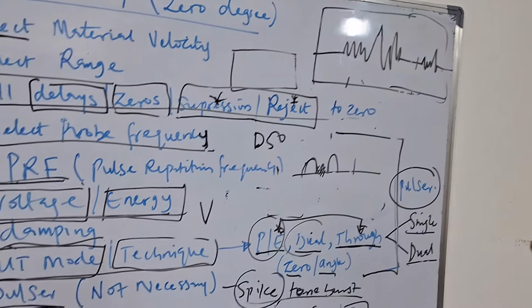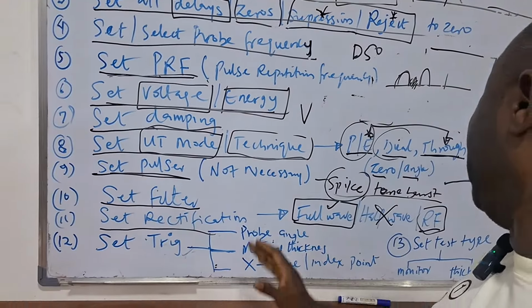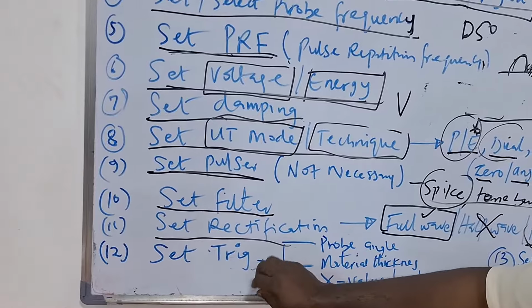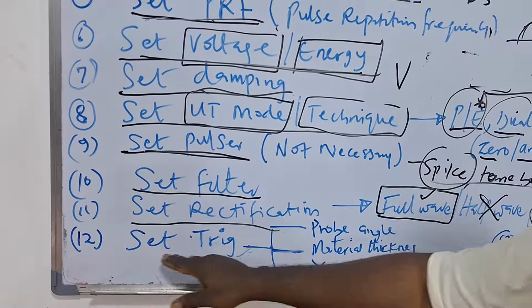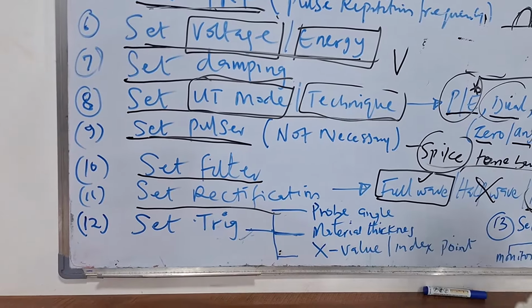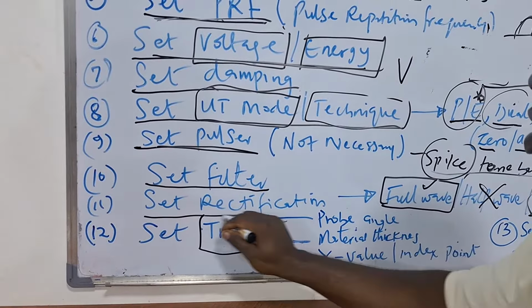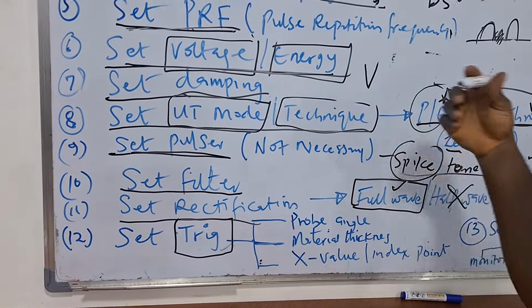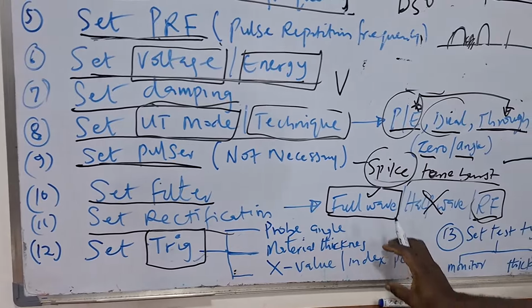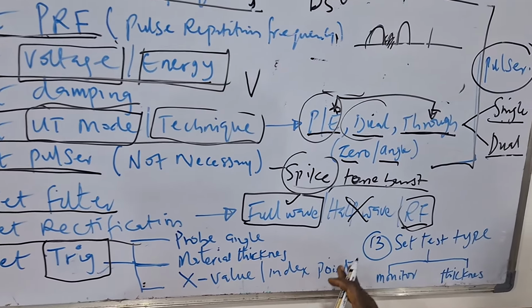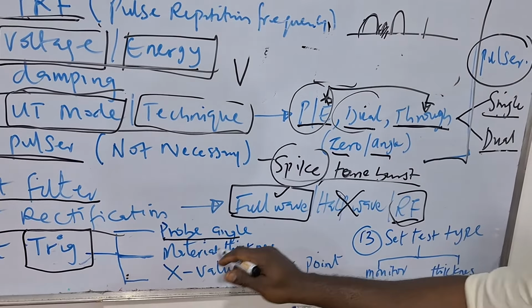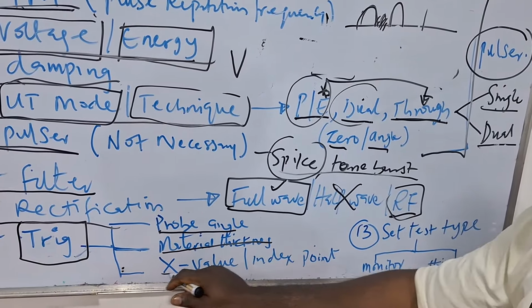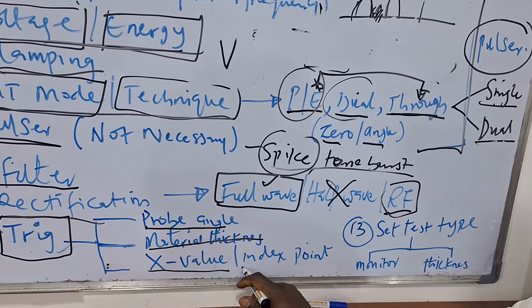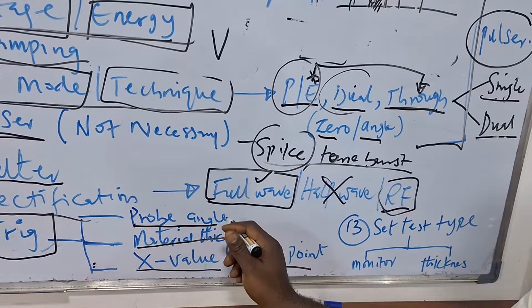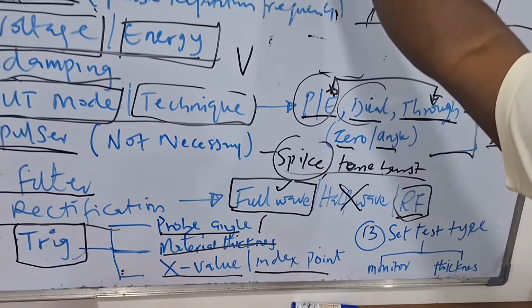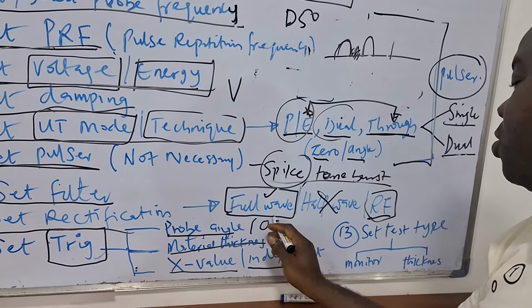The last thing you're going to set, which is very vital, is your trig. Some units put it under a menu called trig, others scatter it across the machine. This is ultimately what affects your result at the end of the day: your probe angle, your material thickness, and your X-value, which some machines call index points. Your probe angle, since you're doing 0 degree, is always going to be 0.